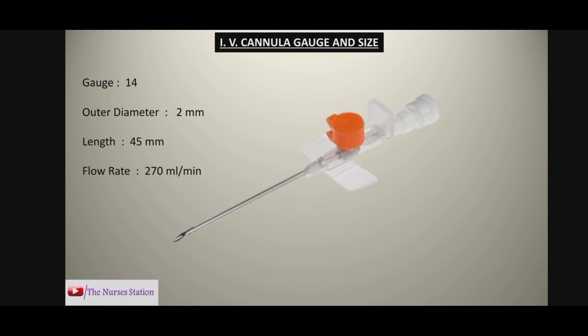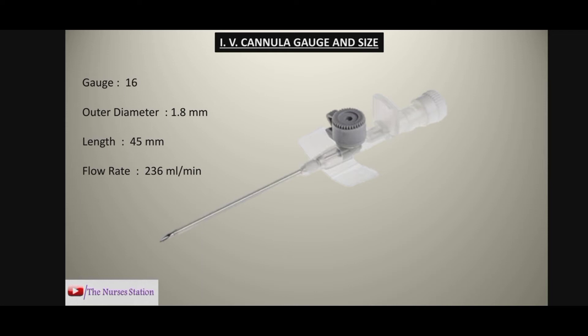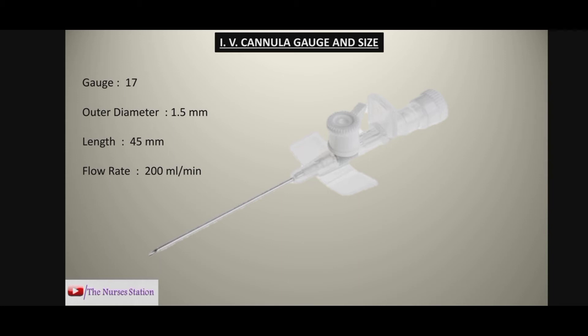The first is the orange colored cannula. This has a gauge size of 14, an outer diameter of 2 mm, a length of 45 mm, and a flow rate of 270 milliliters per minute. Then we have the gray colored cannula with a gauge size of 16, outer diameter of 1.8 mm, length of 45 mm, and a flow rate of 236 milliliters per minute.